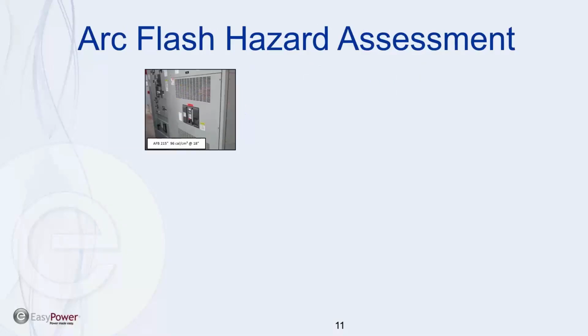So at arc flash level, this was an arc flash hazard assessment that was done for a plant that had old switchgear, and then a new company bought the plant and decided to replace all the switchgear and get smaller switchgear, because they didn't need the 4,000 amp switchgear that was there. So they put in 1,500 amp switchgear and all new panels going downstream. They thought it would be a much lower arc flash level because it's a much smaller switchgear.